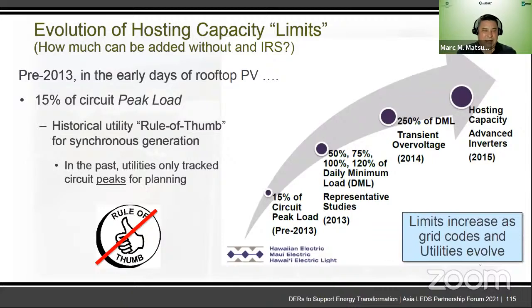So we went, and as the connections grew, we pushed that limit up and up and up. So 50, 75, 100, 120% as we tried to get more comfortable with it. We actually ran into a kind of hard limit of 120%. And then we had to kind of lean on inverter manufacturers to say, hey, you need to address the over voltage issue caused by the inverter. And once they did that, and we put that in our interconnection requirements, then we went up to 250.